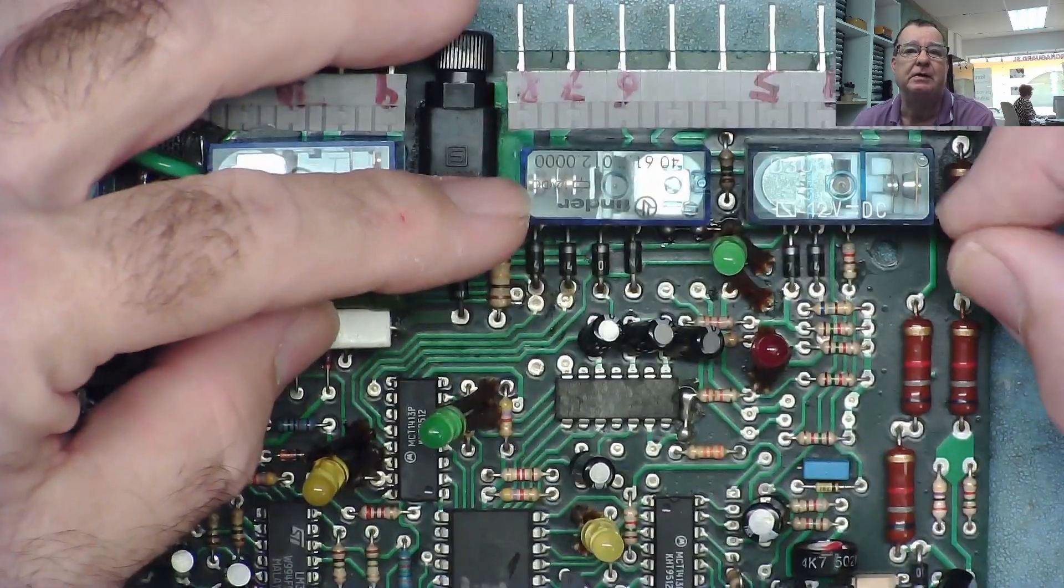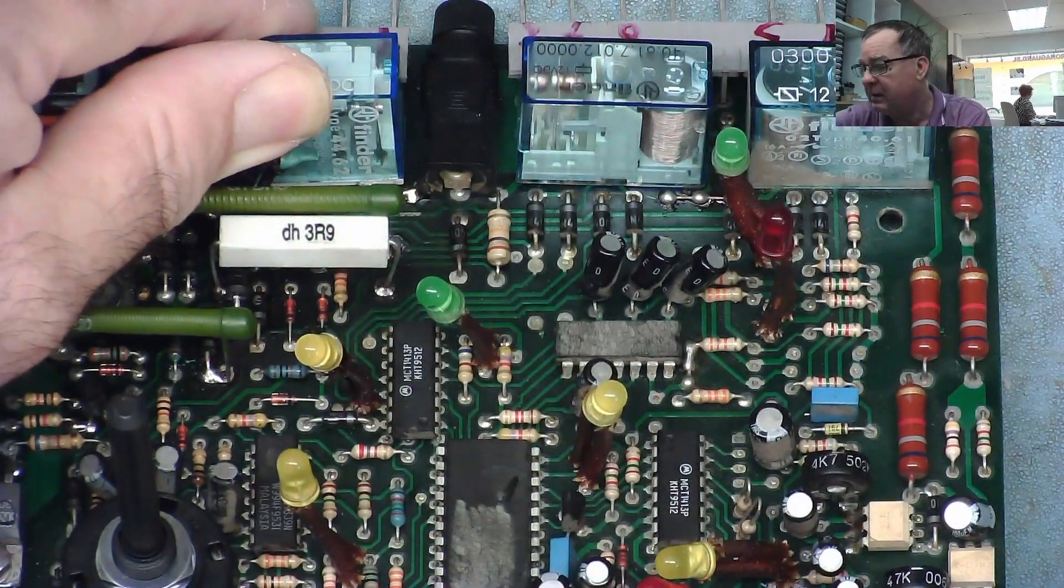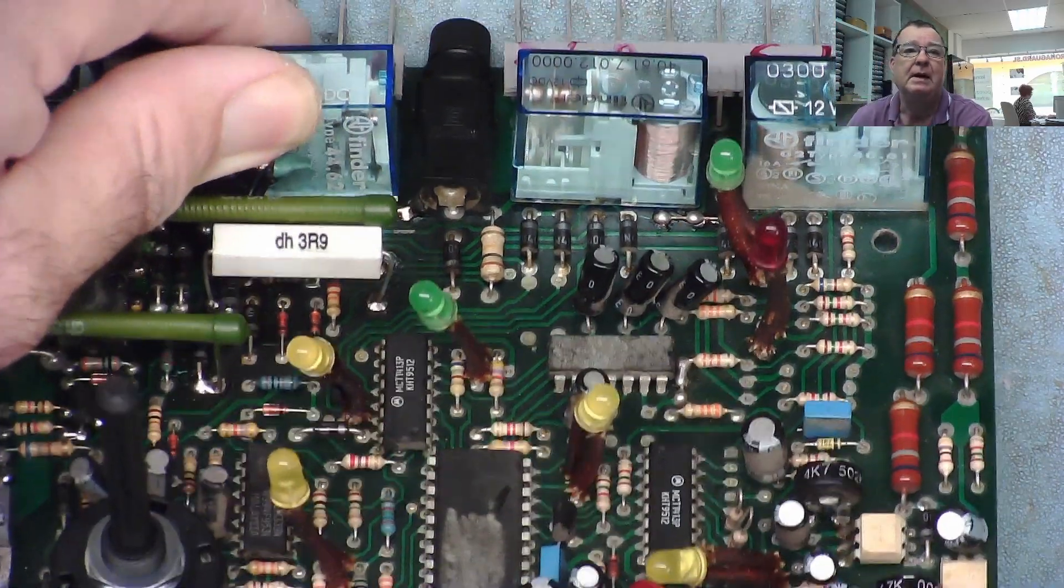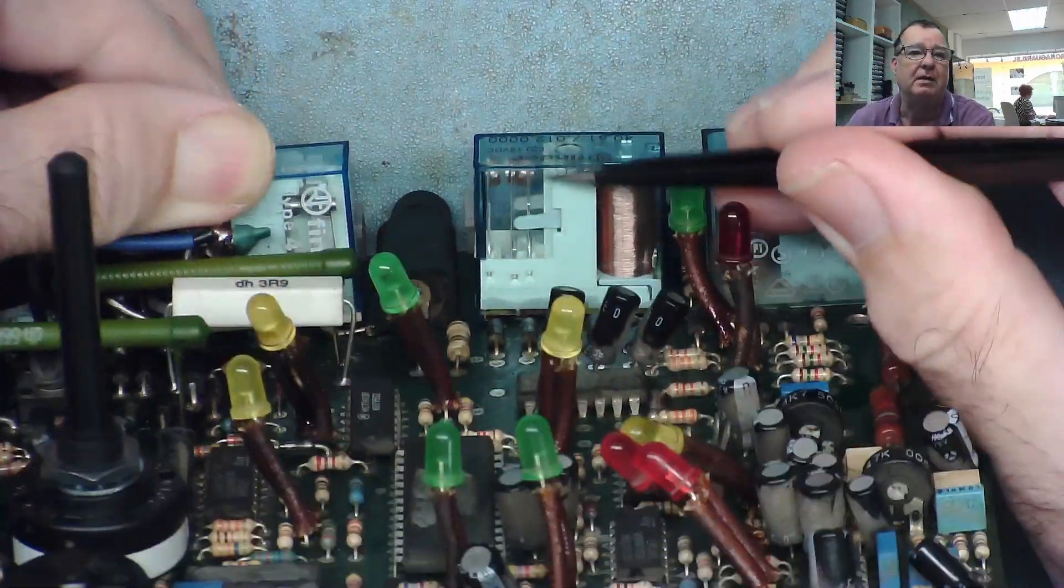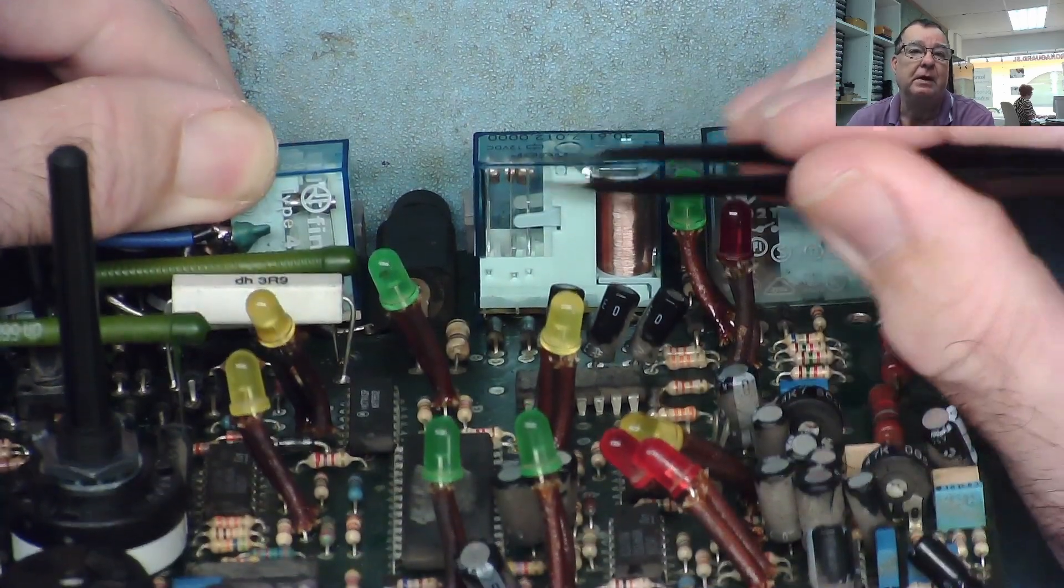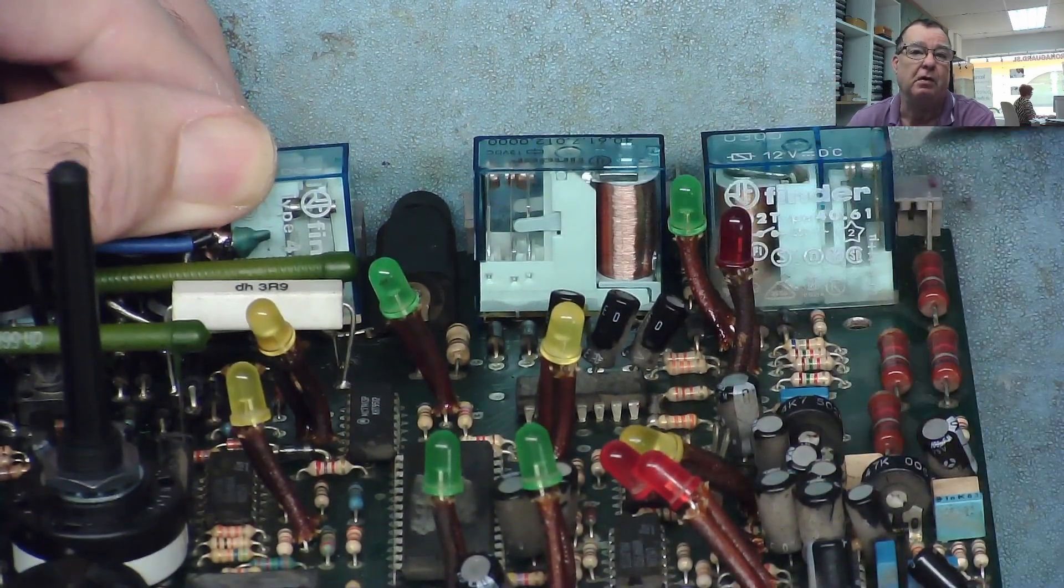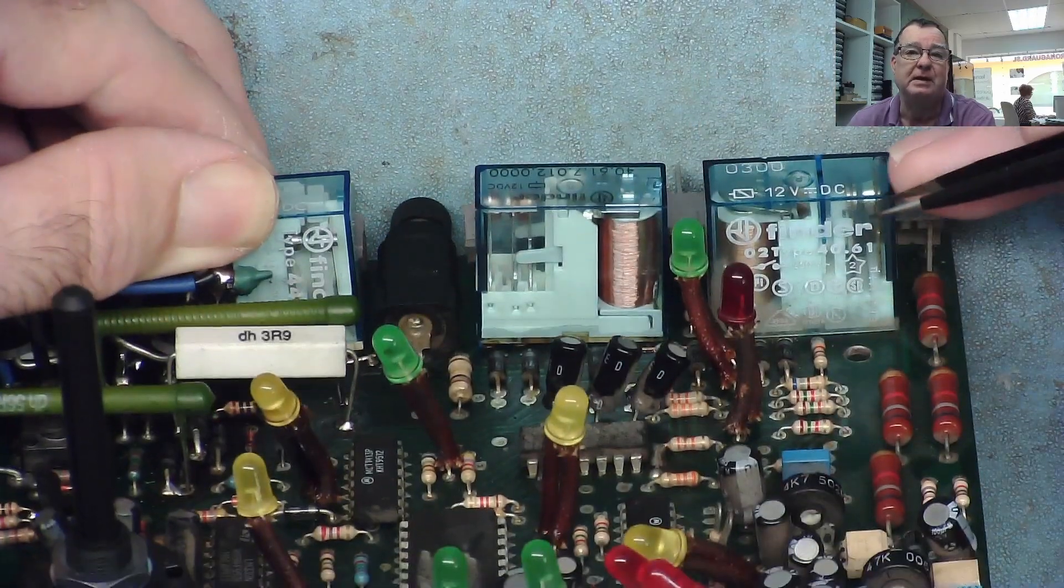So although that's actually a changeover, and this makes a contact, this contact has not been used. So it effectively works the same. So if you don't have the exact relay, you can just do this, or you could just keep this type in stock, and it will work for this type and for this type.